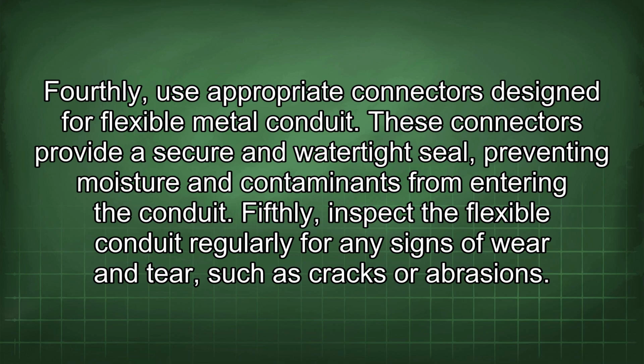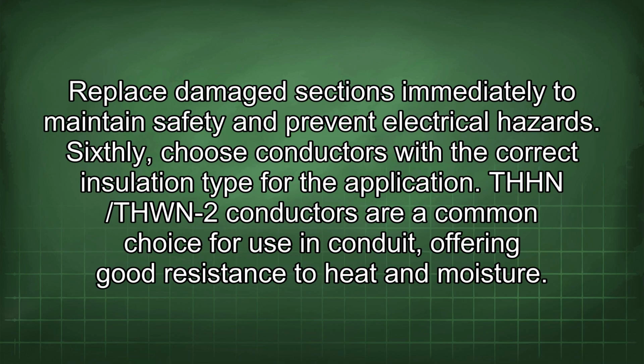Fifthly, inspect the flexible conduit regularly for any signs of wear and tear, such as cracks or abrasions. Replace damaged sections immediately to maintain safety and prevent electrical hazards. Sixthly, choose conductors with the correct insulation type for the application. THHN/THWN-2 conductors are a common choice for use in conduit, offering good resistance to heat and moisture.